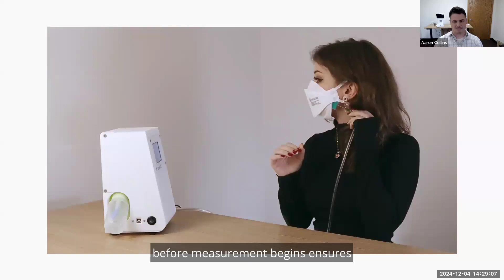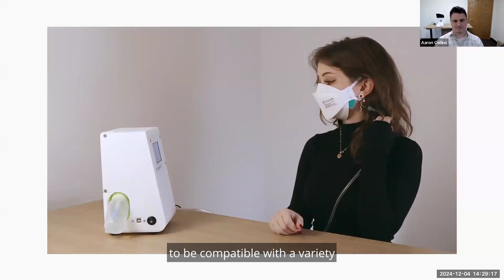A small wiggle of the probe before measurement begins ensures that the medical-grade silicone is well seated between the face and the mask seal. OpenFit's flexible probe is specifically designed to be compatible with a variety of facial features, working well for soft jawlines, strong jawlines, a variety of skin textures, and facial hair. Next, OpenFit purges the line to remove any particles that may remain from the ambient sample. Once the purge has been completed, the in-respirator sampling begins.